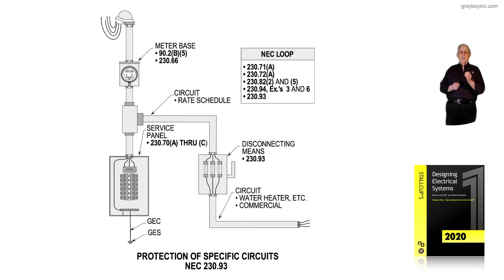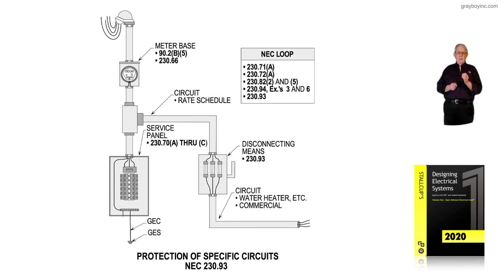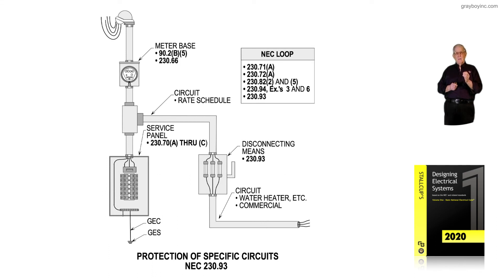Also, 230.94 exceptions 3 and 6 are being applied. We're complying with 230.93, tapping ahead of the main in accordance with 230.82. We are grouping the disconnecting means, switched together in accordance with 230.71 and 230.72A, which basically says you can have 2 to 6 mains grouped, as you see in the illustration.